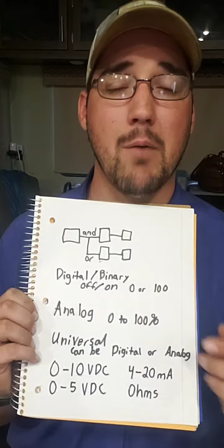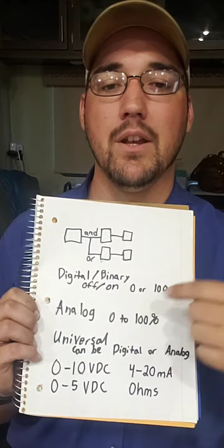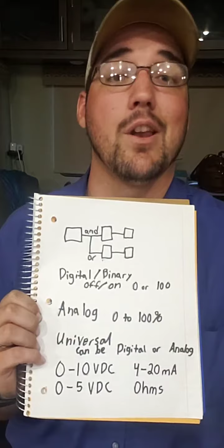Now, keep in mind, guys, these aren't all of the signals that can be received, but for the most part, 98% of the systems you're ever going to run into out there, if not 100, depending on how much exposure you get, are going to be somewhere on this page. They're going to fit these parameters. They're going to fit everything we've talked about. So when you start looking at controllers, start looking at these different AOs, AIs, DOs, DIs, or UOs and UIs to know what could be running off of that point. That really can help go a long way when you're trying to trace things out, or when you're trying to figure out how this is supposed to work, or how it is supposed to do what it's doing. Knowing if it is an input or output can really help you determine what component could be hooked up there, whether it be a thermistor, a contactor, a relay, whatever.